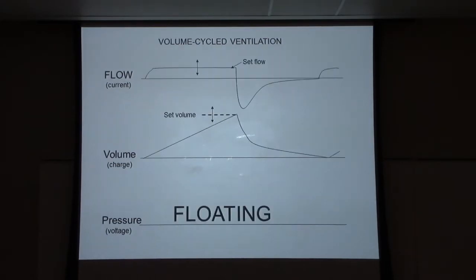So I'll show you some examples. This is volume cycle, and what you can do is set it to different higher flow or lower flow, higher volume, lower volume. You can change the shape from flat like this to sinusoidal or descending. So these are the controls on the ventilator.